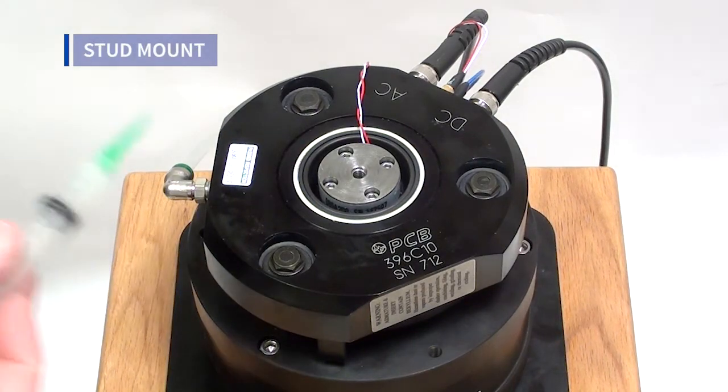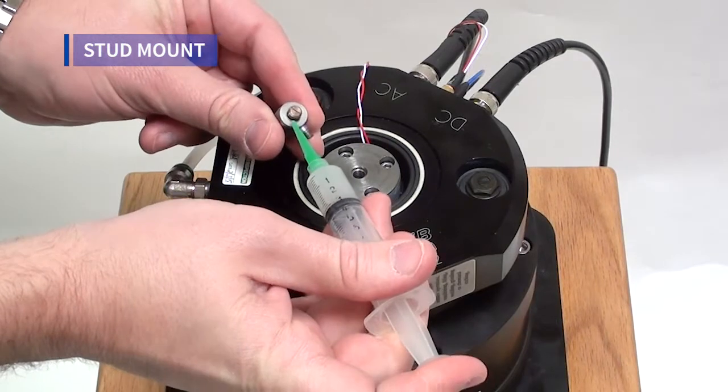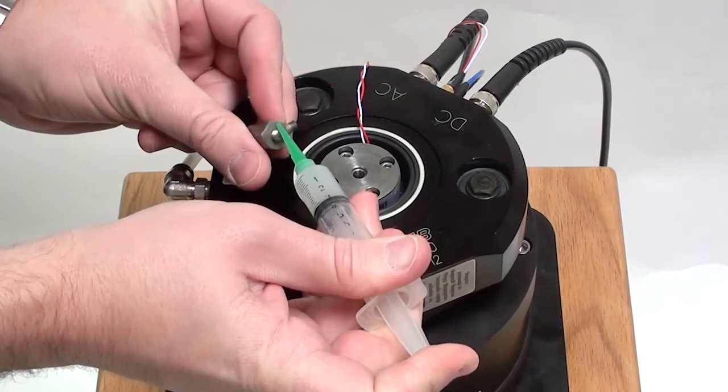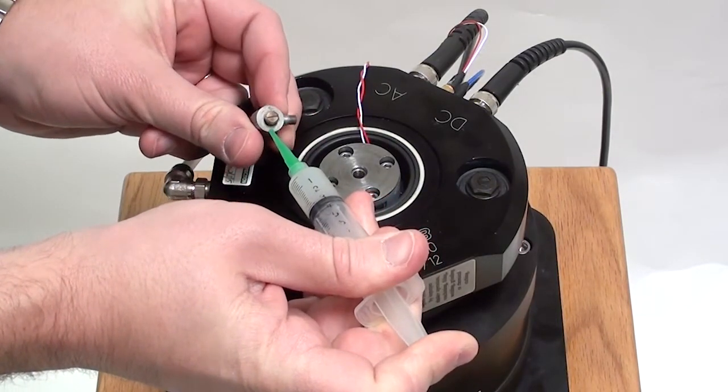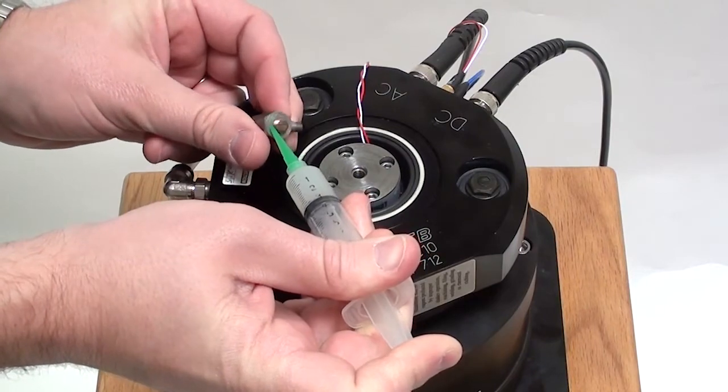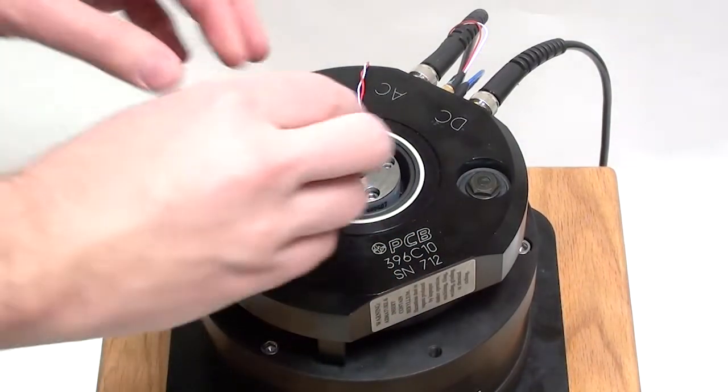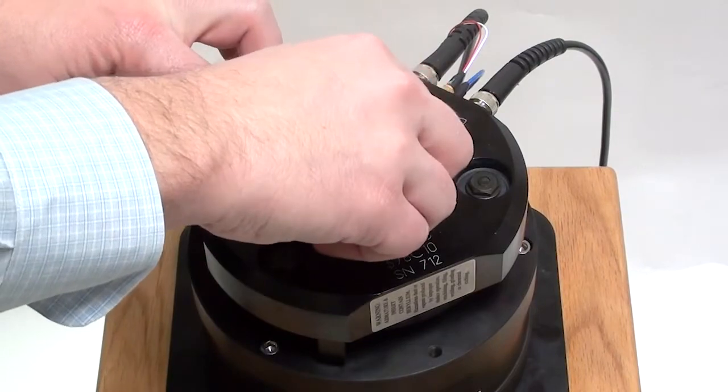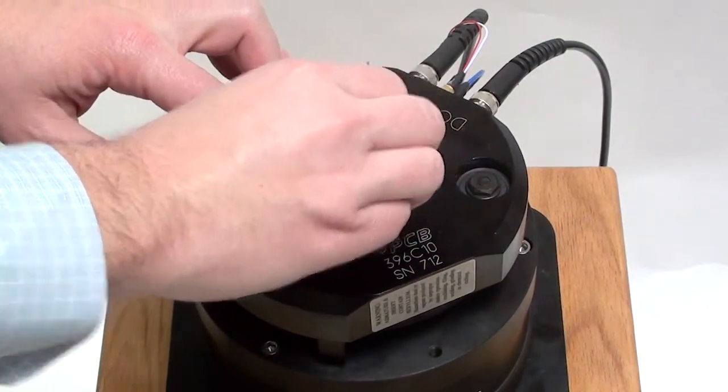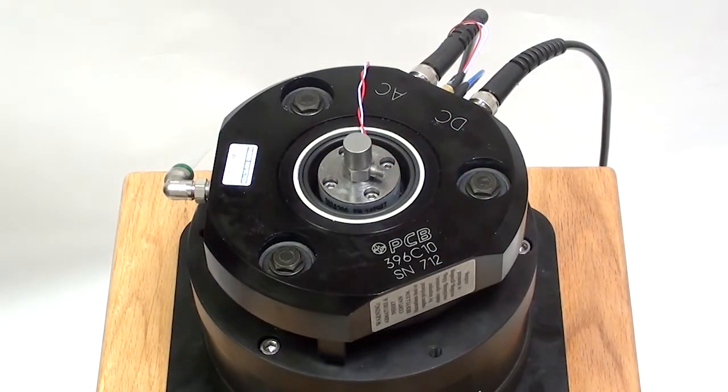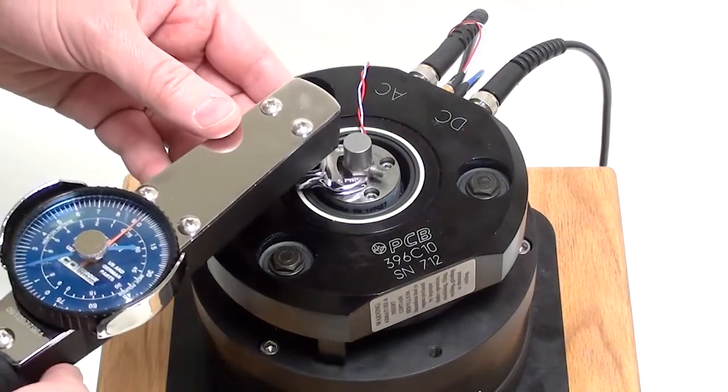For stud mounting, apply a small amount of gap-filling silicone grease to the mounting surfaces. Then, thread the accelerometer to the mounting hole with the mounting stud and apply the appropriate torque.